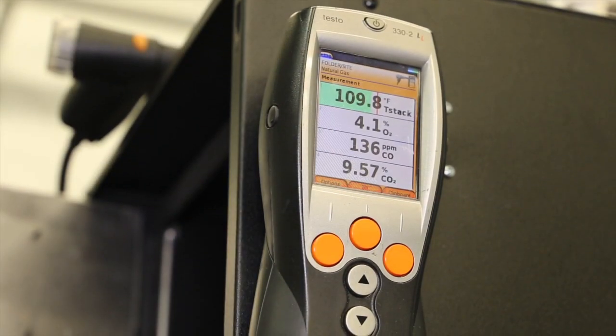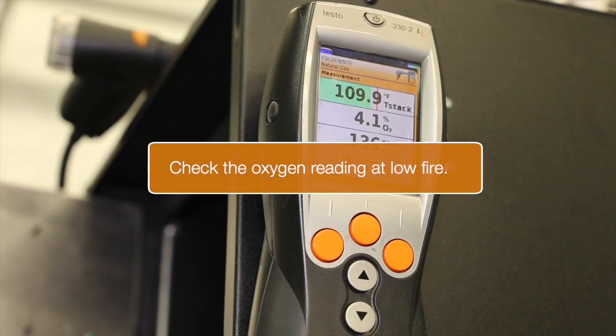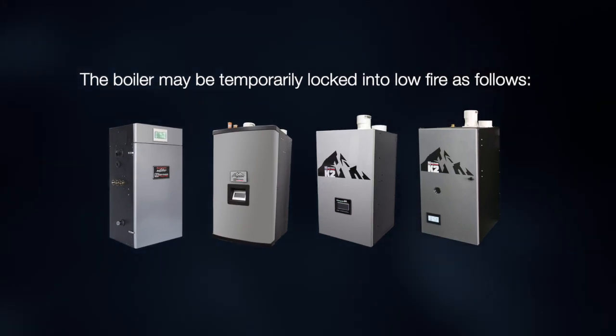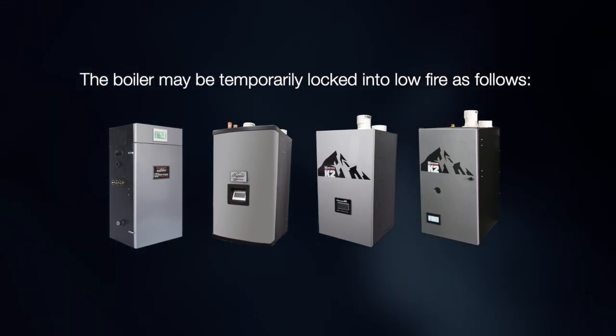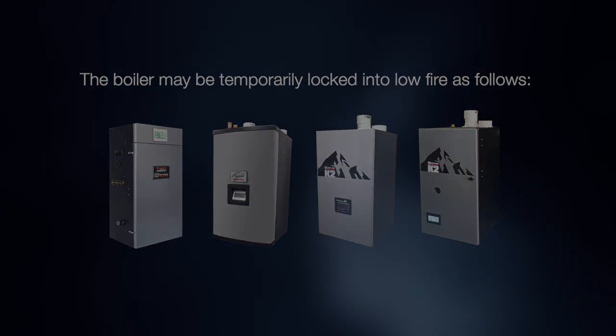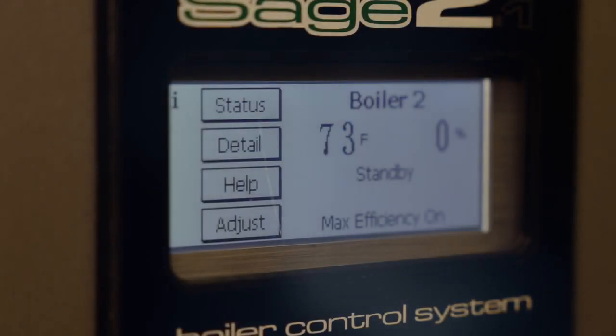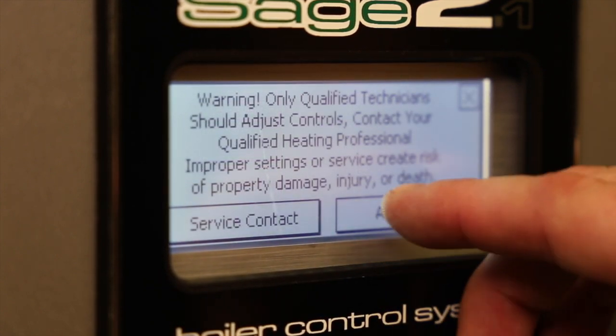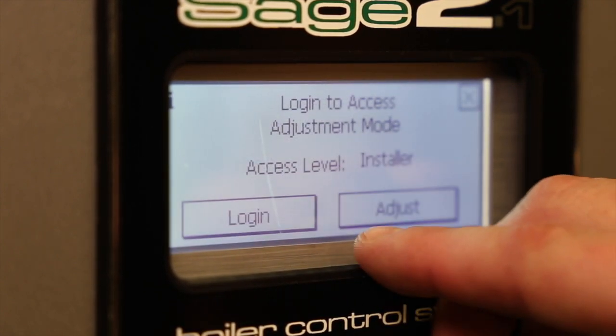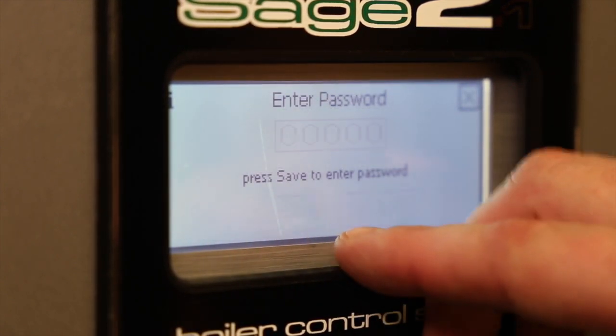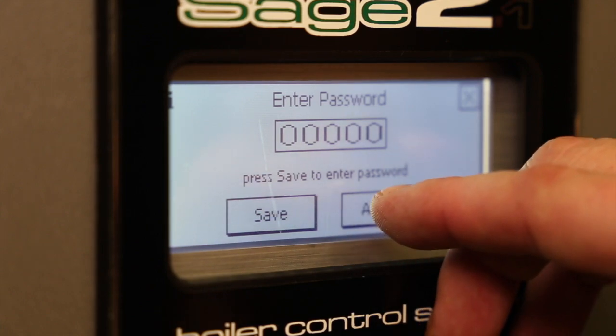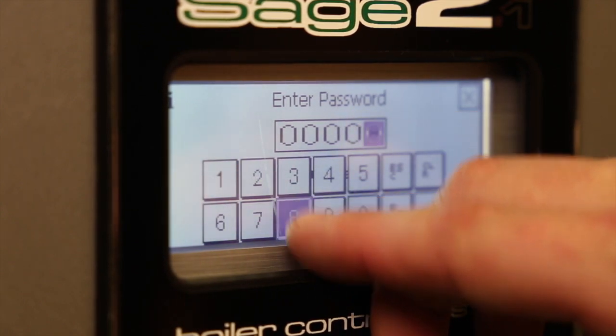Next, check the oxygen reading at low-fire. The boiler may be temporarily locked into low-fire as follows. From the home screen, press adjust and press adjust again. Press login, press the box containing 000.